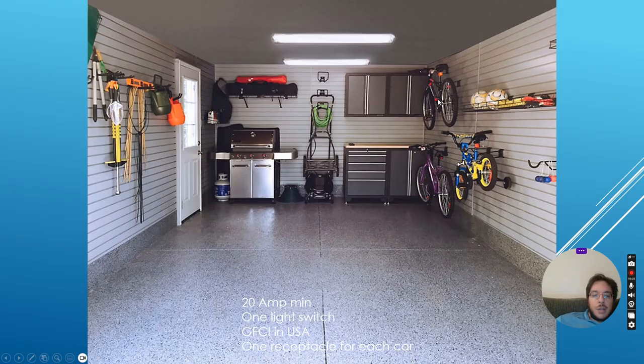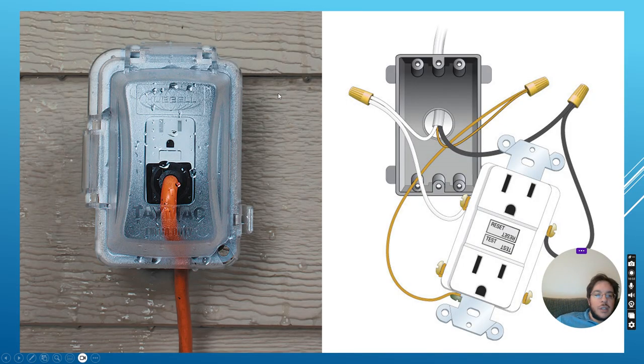Now, your garage, so some people have a sub panel in their garage, which is good, and then they can take all the garage circuits off the sub panel, and some people don't. Doesn't matter. Now, in the US, a garage must be GFCI rated and 20 amp minimum. You need a light switch. You can put receptacles, garage door opener, and lighting on the same circuit, and you want to have a receptacle for your garage door opener within 1 meter or 3 feet of your garage door opener. And in the US, you need an additional receptacle for each car space. So if you've got space for 2 cars, then you need 2 wall receptacles. It's good practice to have. And then you need one circuit for the outdoors, and it's got to be weatherproof, or in a weatherproof box, and all receptacles must be GFCI rated.